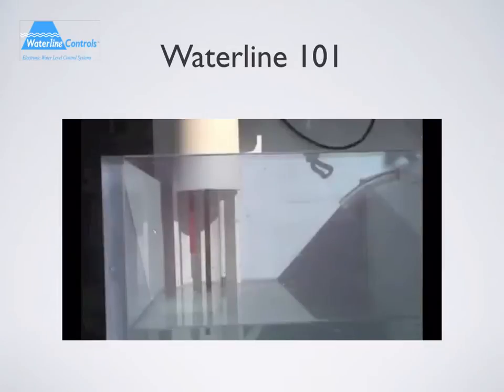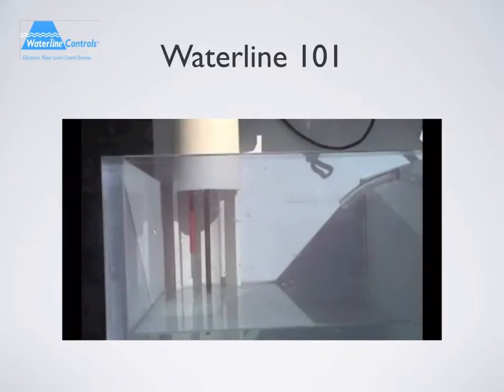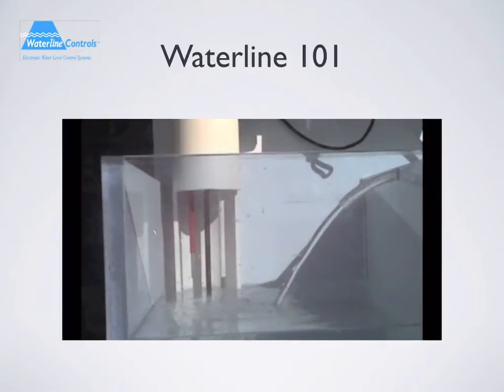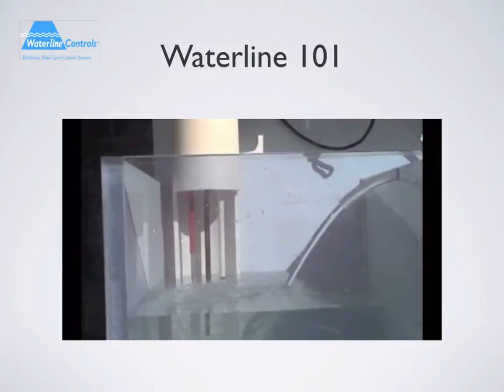Here we have a Waterline Controls model in action. This is a WLC 3000 sensor wired to its controller. This model's sensor consists of three probes. The software will fill the tank to a specific level, then turn off the valve. What you're seeing is water moving away from the white probe on the sensor, which turns on the fill valve. The controller will run a six-second timer before activating the fill valve to ensure accuracy. Once the water hits the red probe, the controller turns off the valve. It is that simple.